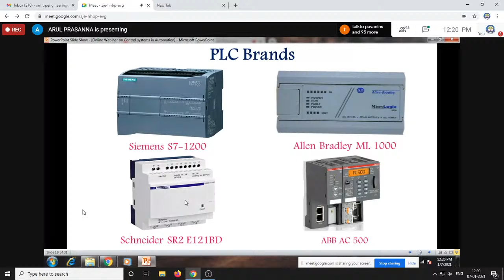Next, how do we select a PLC? We know what a PLC is and how we are going to use it. How do we select a PLC before getting into the project? First we must know whether we are going to use only digital inputs, or whether our project will involve analog values. Once that is confirmed, we can select the PLC depending upon our application. That means how many digital inputs and how many analog inputs we need, and depending upon that we can select a module of the PLC. Similarly for outputs. Next comes the memory: how much memory your program or process is going to need.